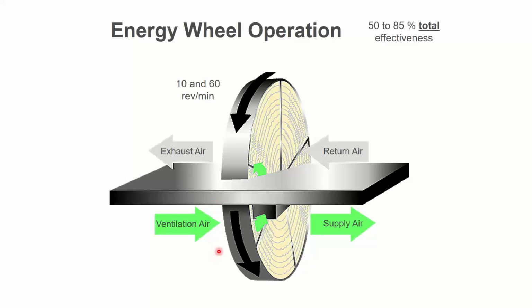But there's going to be a filter here on the ventilation air and a filter on the return air leaving, which seems weird. I'm filtering the exhaust air out. Yeah, because I don't want any dirt to get on the heat exchanger. Those filters have to be maintained and cleaned regularly, or maintained and changed regularly.